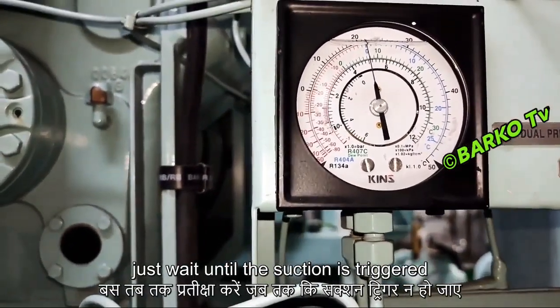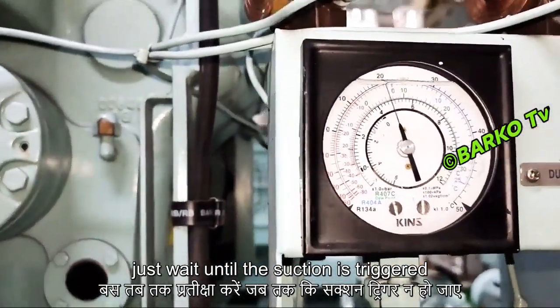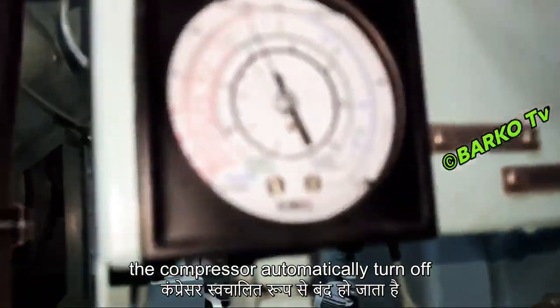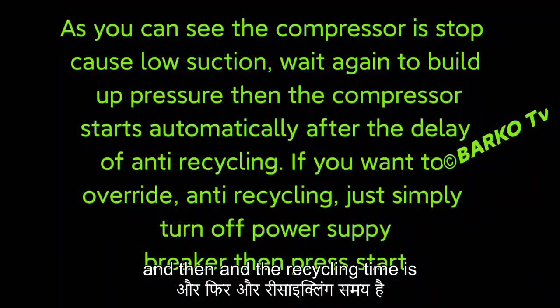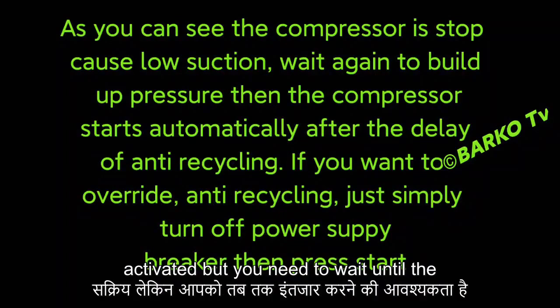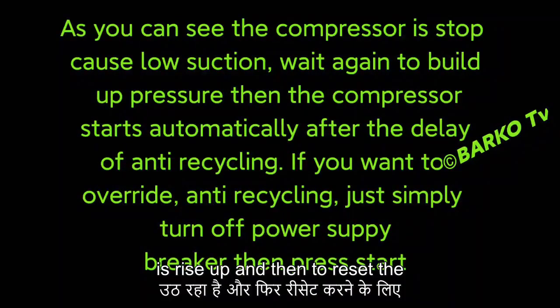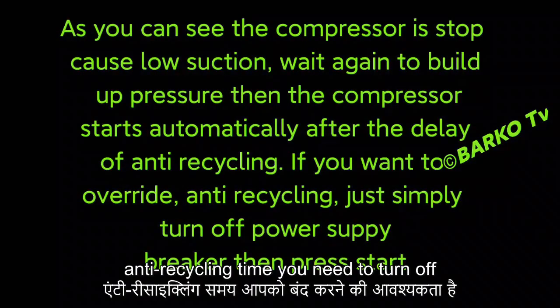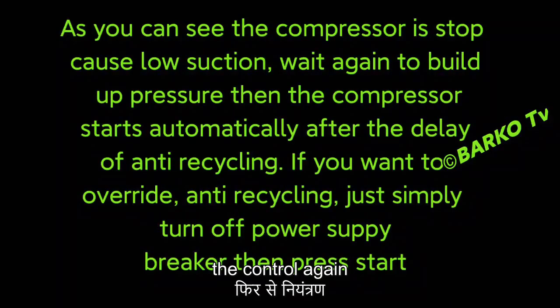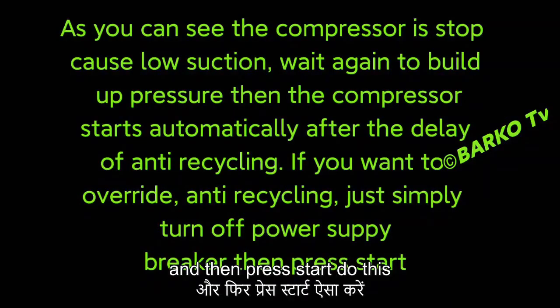Just wait until low suction is triggered. The compressor automatically turn off and then anti-recycling time is activated, but you need to wait until the pressure rise up, and then to reset the anti-recycling time you need to turn off the control again and then press start.